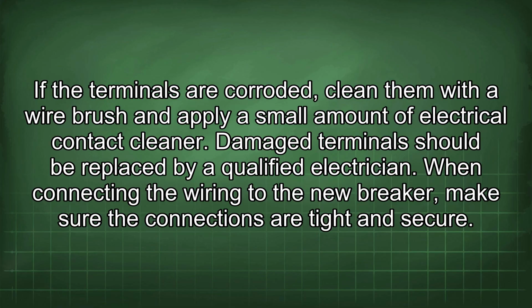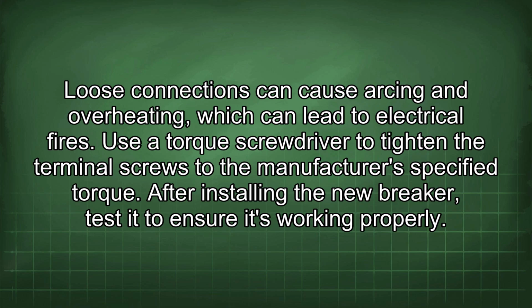When connecting the wiring to the new breaker, make sure the connections are tight and secure. Loose connections can cause arcing and overheating, which can lead to electrical fires. Use a torque screwdriver to tighten the terminal screws to the manufacturer's specified torque.